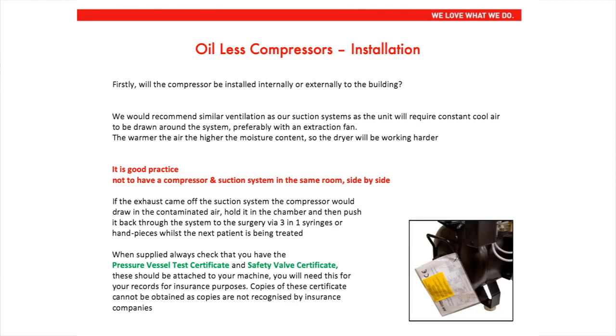It is good practice not to have a compressor and a suction system in the same room side by side. If the air exhaust came off the suction system, the compressor would draw the contaminated air, hold it in the chamber and then push it back through the system into the surgery via the 3-in-1 syringe or the handpiece while the next patient is being treated.